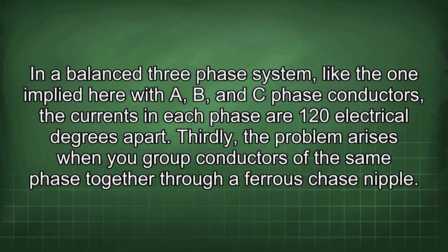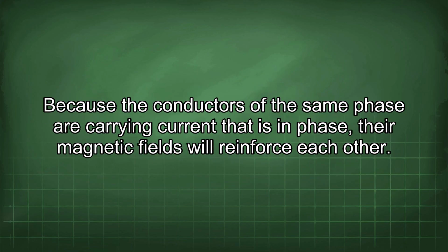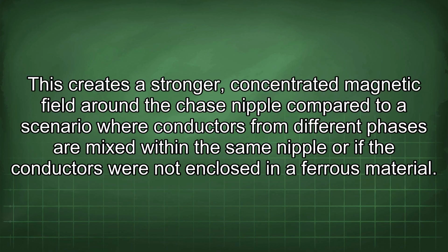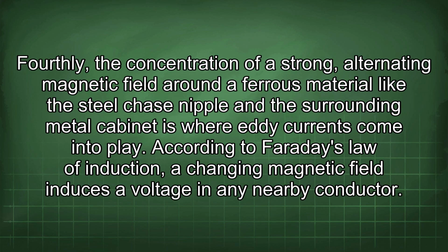Thirdly, the problem arises when you group conductors of the same phase together through a ferrous chase nipple. Because the conductors of the same phase are carrying current that is in phase, their magnetic fields will reinforce each other. This creates a stronger, concentrated magnetic field around the chase nipple compared to a scenario where conductors from different phases are mixed within the same nipple, or if the conductors were not enclosed in a ferrous material. Fourthly, the concentration of a strong, alternating magnetic field around the ferrous material, like the steel chase nipple and the surrounding metal cabinet, is where eddy currents come into play.